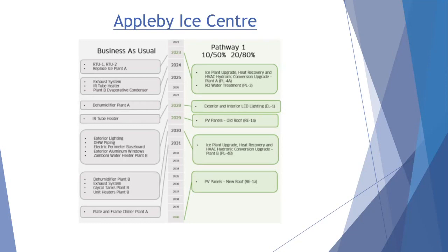The current ice rink refrigeration system, is it ammonia based? Yep. Okay, so have you considered a CO2 based system? What sort of analysis went into the refrigeration system upgrade? We didn't look at CO2—I think that might be something we'd look at more in the detailed design of that measure, but right now it was just back with an ammonia plant. I think that was more at the request of the operations teams, because that's what they're used to. Too much change, not good.